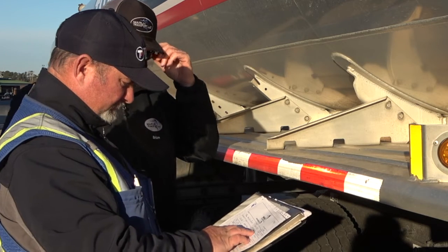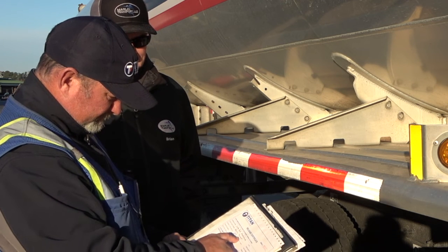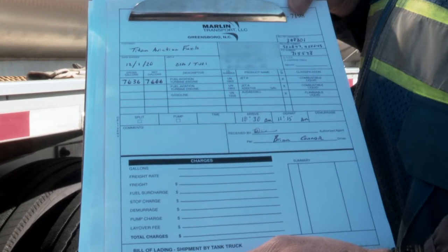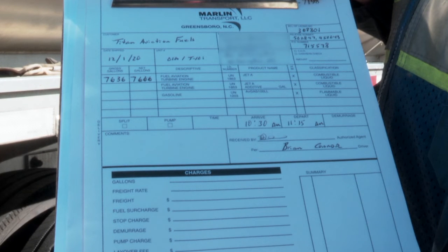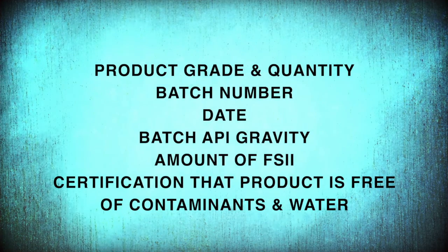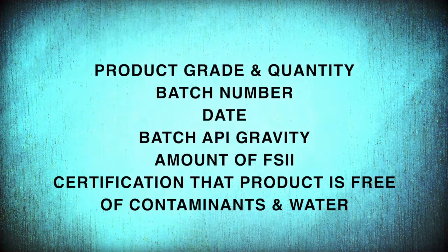While the transport is settling, the driver contacts the airfield representative to begin the pre-discharge inspection and check the documentation. The driver hands over the product release certificate, certificate of analysis, and the bill of lading. Never assume anything. Both the driver and the airport representative should verify the product on the truck is the product ordered and that the bill of lading is accurate. The release certificate and bill of lading contain the following: product grade and quantity, batch number, date, batch API gravity, the amount of FSII, and certification that the product was free from contaminants and water after loading.